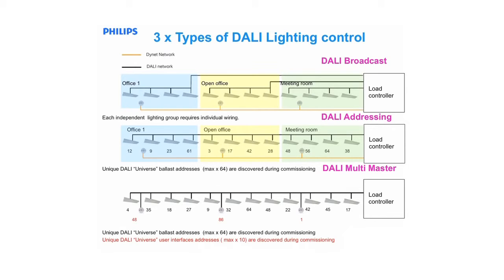This way, the sensors do not take away from the maximum 64 ballasts that can be used. As before with the DALI addressing system, a commissioning technician will find the individual DALI address fittings and then group the fittings into logical areas. Once those areas have been defined, the sensors will also be assigned to those areas.